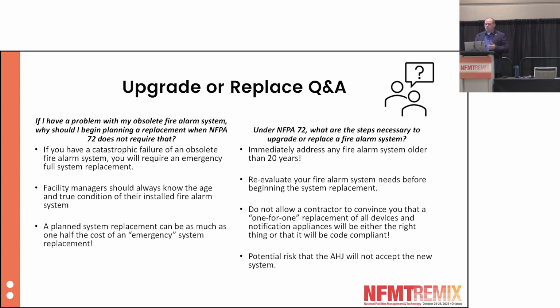Facility managers should always know the age and condition of their installed fire alarm systems so they can plan for planned upgrades or replacements. A planned system upgrade will cost as much as half the cost of an emergency system replacement. The headaches alone are worth the planning in advance. The fire watch, the overtime, all of the other things that go into an emergency fire alarm system replacement are painful at best.